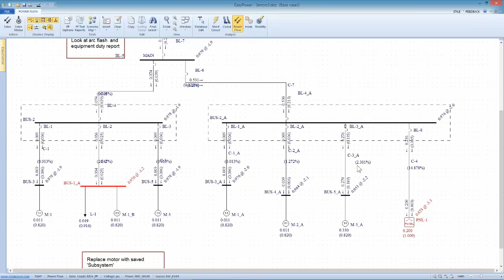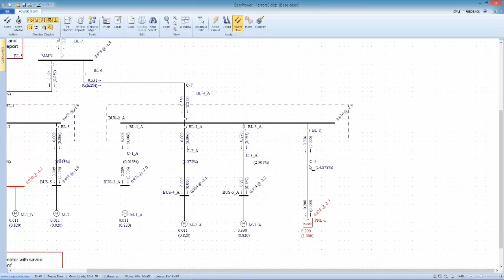with results that say, okay, yeah, we've got normal operations. If we have a discrepancy between the voltage levels that are measured and the voltage levels that are predicted by the power flow study, this can indicate a problem with the way the model's been constructed. Whether it's data collection or data entry is a function of where we stand, but the power flow is the backup error checking to verify that we haven't made some kind of gross error. Here we're seeing that this bus has about a 20% drop in voltage, and when we took the readings, that wasn't the case in the real system. So that would make me think to go back and verify what's going on with this cable.